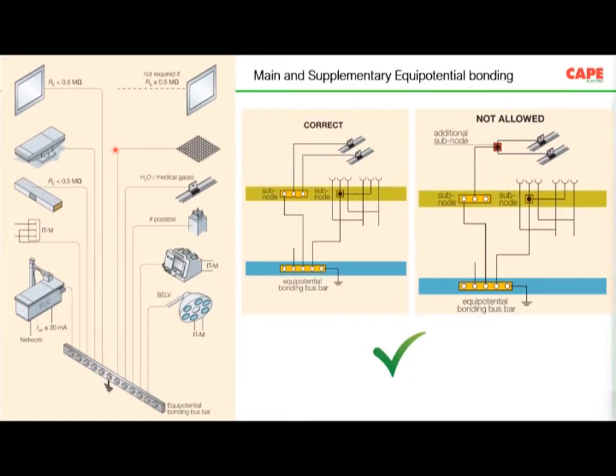In the picture, I am just showing how to make it, but there are several rules to be followed. Say, for example, after making the supplementary equipotential bonding, take this particular medical gas pipe and the bus bar: the resistance between the medical pipe and the earth bus bar must be less than 0.2 ohm. So measurements are required, the joint measurements are required. So basically, the rules for supplementary equipotential bonding are very much mandatory for medical locations, group 1 and group 2 medical locations.